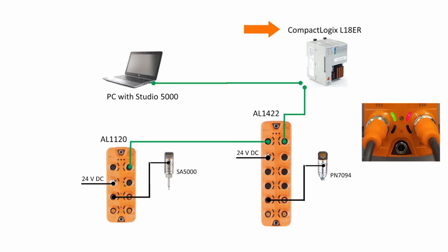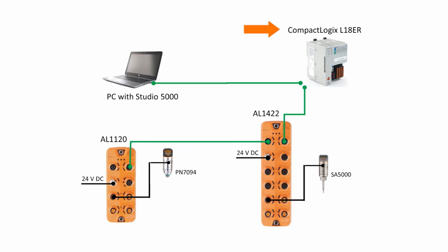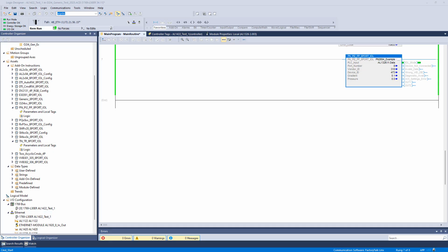Fixing this error requires one of two solutions. The first solution is connecting the correct part number to the AL master port with the matching device ID. The second solution would require a programmer to access the PLC project and reconfigure the device replacement settings to match the new device. Let's take a look at an example.